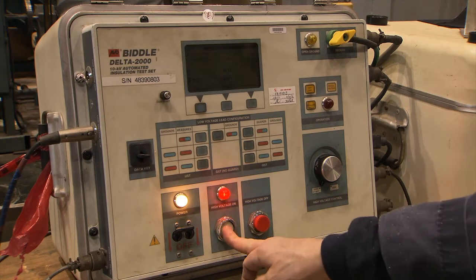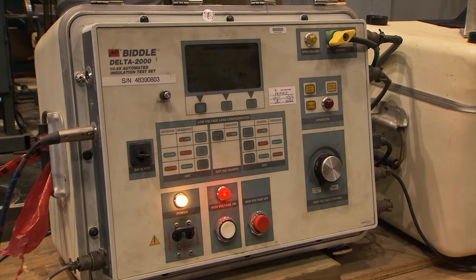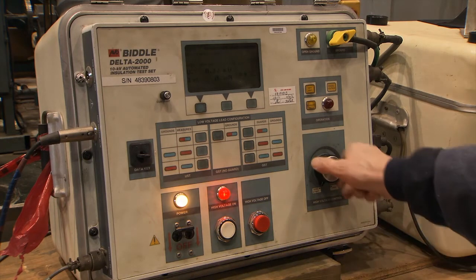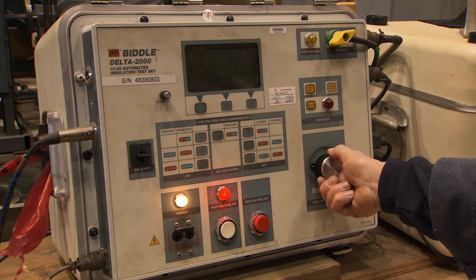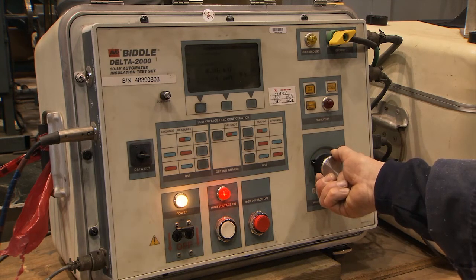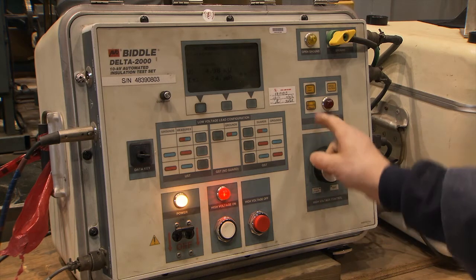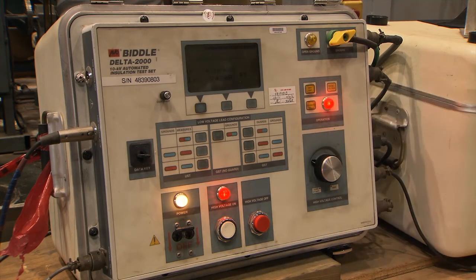Press the high voltage on switch and the red light goes on above. Turn the high voltage control knob to the set point of 5 kilovolts indicated on the digital display window. Press the measure button on the operation panel and the red light beside it goes on.